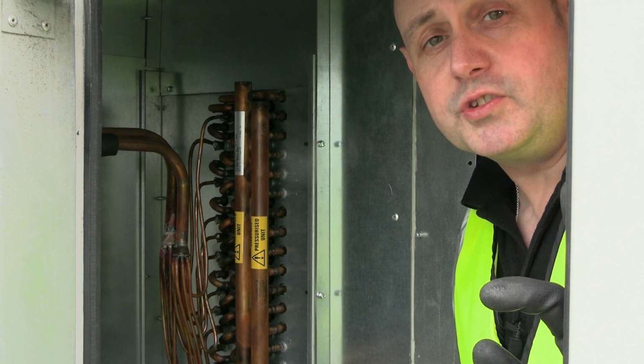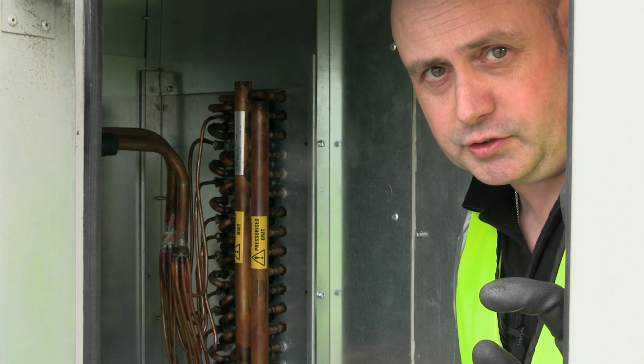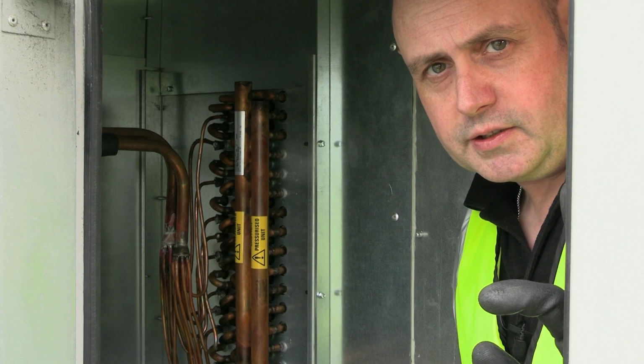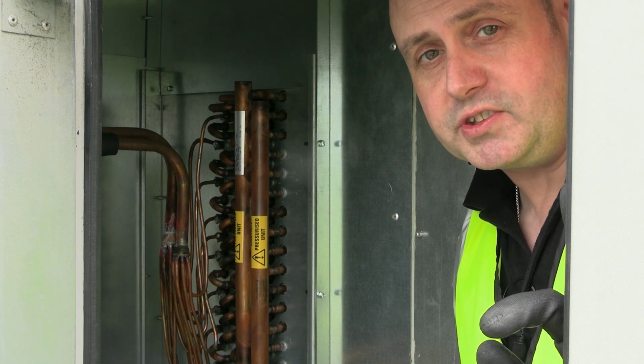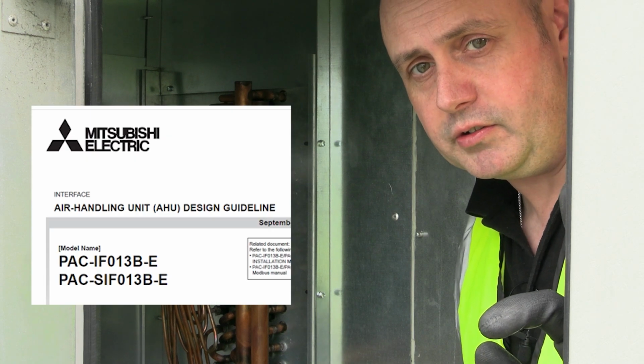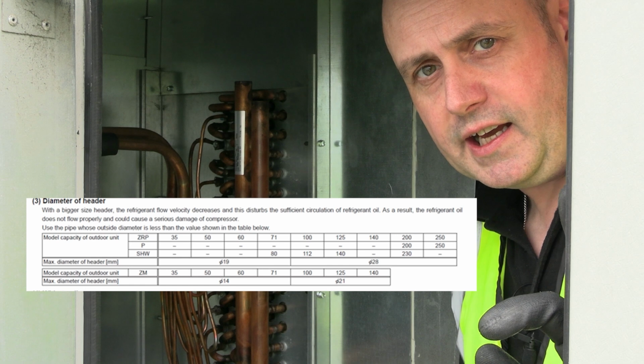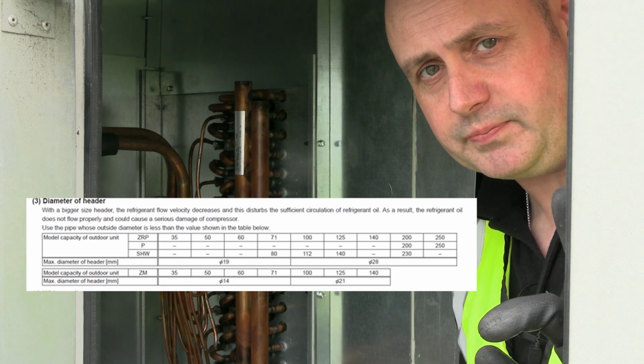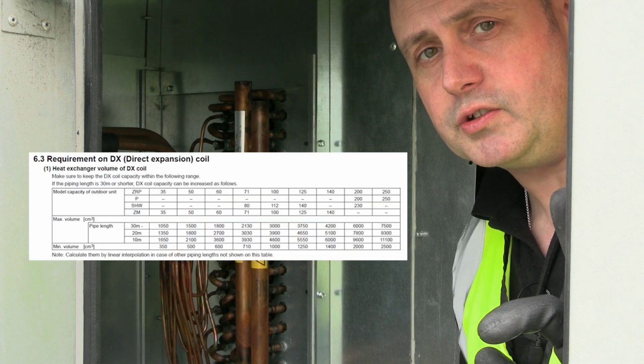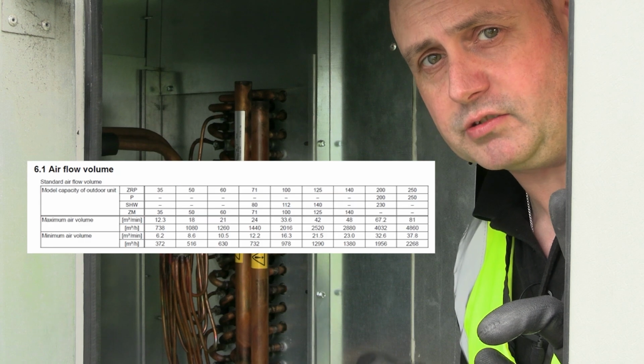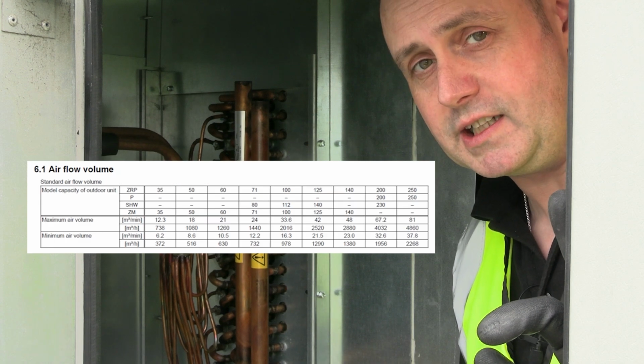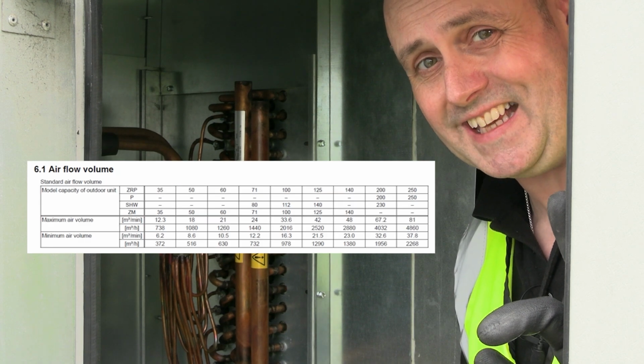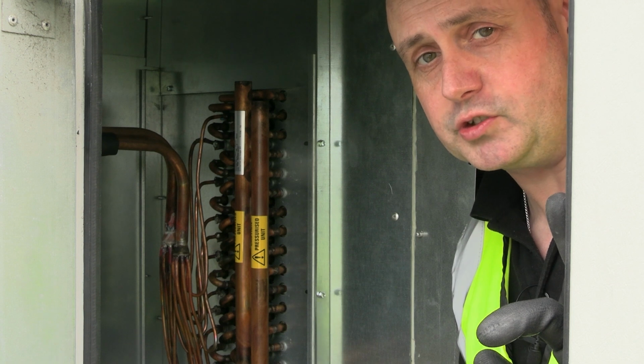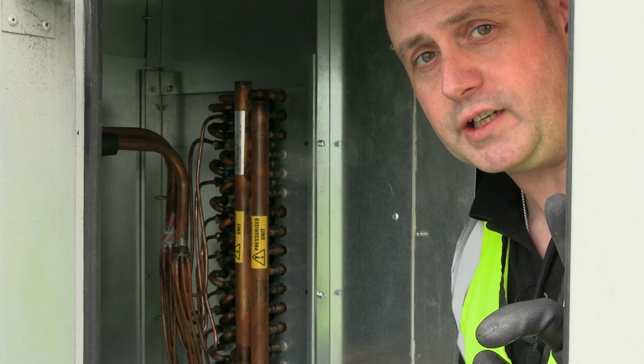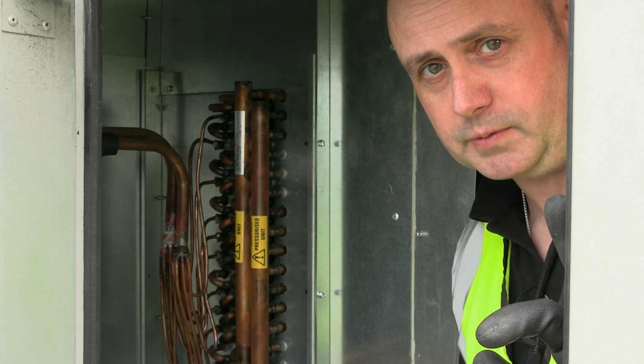The AHU coil design is critical for how these units work. We've got AHU guidance documentation. I'm showing a little bit of that just beside me. And getting that pipe size correct, getting the volume within that coil spot on, and getting the airflow correct, for this all to work together is really important. So make sure that's nailed. If you're not too sure, you can always give Mitsubishi Electric a call and we can go through that coil design and make sure it's all going to work.